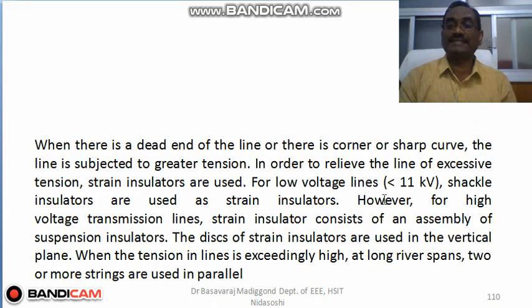For low voltage lines, that is less than 11 kilovolts, Shackle insulators are used as strain insulators. If the working voltage is greater than 11 kilovolts, then we use strain insulators. However, for high voltage transmission lines, strain insulators consisting of an assembly of suspension insulators are used. The discs of strain insulators are used in the vertical plane when the tension in lines is exceedingly high. At long river spans, two or more strings are used in parallel. Okay.